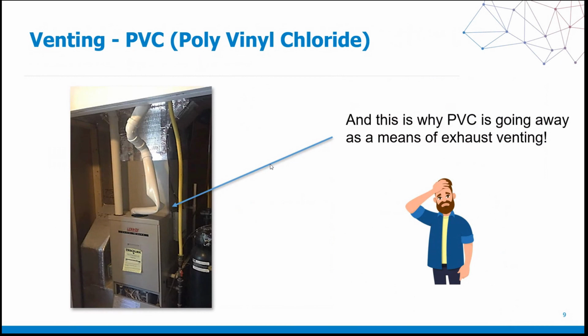Venting. It would be remiss of me to talk about combustion analysis if we didn't discuss venting. And as you see here, our beloved PVC, yes, the product that we've all been using for years, otherwise known as polyvinyl chloride, is going away. So if those of you that are viewing this are not aware that it's going away in our industry for venting purposes, it's going away. PVC, in the way that we're using it for exhaust venting on high efficiency or condensing equipment, was never intended to be used this way. It was never designed for the temperature tolerances that we're putting it through. And given that, we are now having challenges with the way the PVC is performing. You're getting odd shapes like you see here in this little serpentine view of a piece of PVC. And we're also not following the specifications on the master glue that we're using to seam it together with its various joints. And we're leaving air pockets in here because we're not following those specifications either.